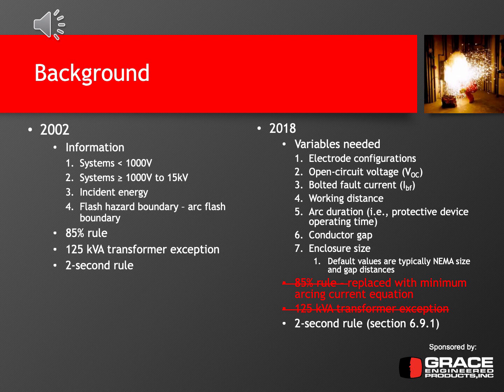2002 also had a 125 kVA transformer rule exception, where if you had a transformer that was 125 kVA or less providing equipment from an upstream position, then you could eliminate or not even perform the arc flash analysis for that downstream equipment that's connected to the 125 kVA transformer.